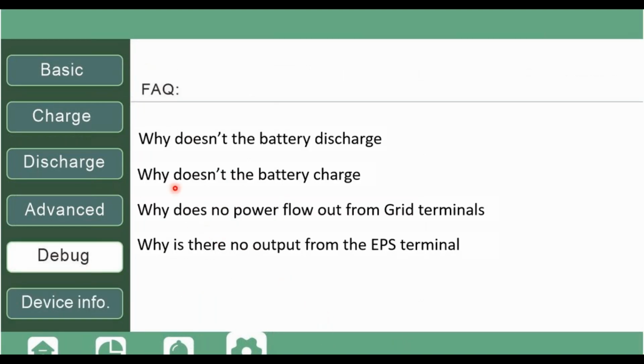Next, you have a little line of defense, let's put it that way. You might be setting your system, and the system is not doing what you think it should be doing. So it has a little debug feature, right? You can select the question why there's no power flow out from the grid terminals. When you click it, it will tell you, for places that have really bad voltage, or the voltage is out of range, or the frequency is out of range.